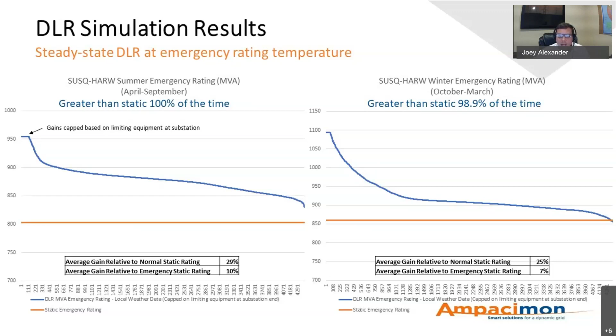So one final thing we do for DLR planning is to determine which spans need sensors. Dave may correct me, I think this line was around 20 kilometers, 79 or 80 spans. We don't need to put sensors on every single span. Really, the important spans to put sensors on are the ones that are going to be the most thermally limiting, that are going to be the bottleneck for that line.